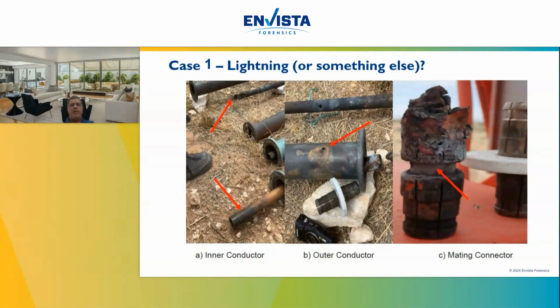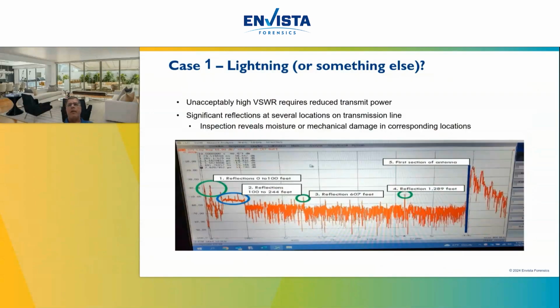Inner conductors are just copper tubes. We see some well-developed heat damage here on these pieces. We see a few holes up near the connectors, and on the right side, in image C, is one of the mating connectors that is actually a burned copy of what you see in the bottom part of image B, with the white disc on it. In this case, that has all melted off, and this is a heavily corroded piece now. That came out of a piece that they replaced. If we think about lightning and arcing, they behave in certainly different ways.